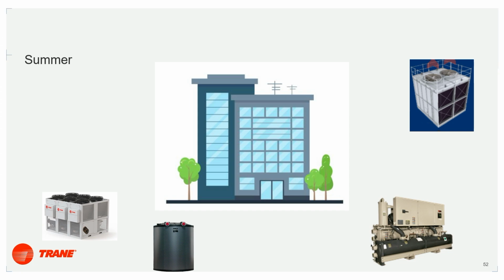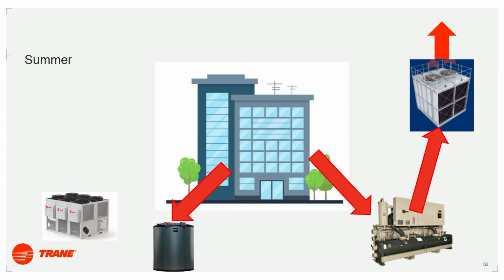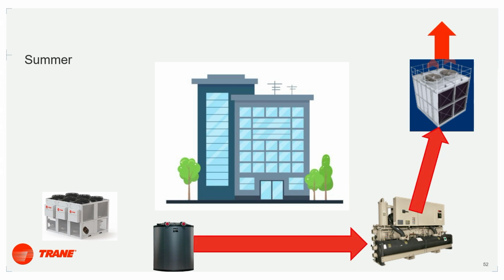We've done ice storage for cooling only applications for 50 years. Ice was the original form of refrigeration. In an ice storage cooling only system, our battery is charged in the morning when our tanks are full of ice. In a typical application, you're going to size your chillers for about 60% of your peak load. 40% of your load is going to be handled by that ice storage. Throughout the day, you are going to reject heat out of the building through your tanks, melting that ice, and the remainder through your chiller tower or air-cooled chiller.